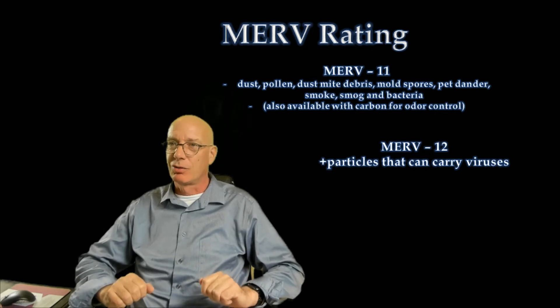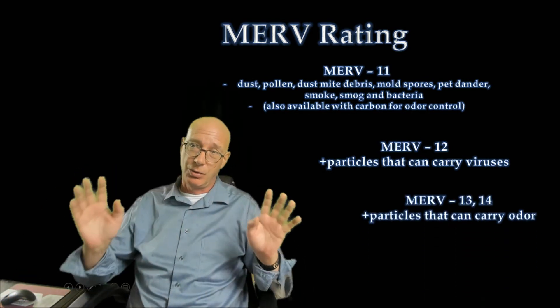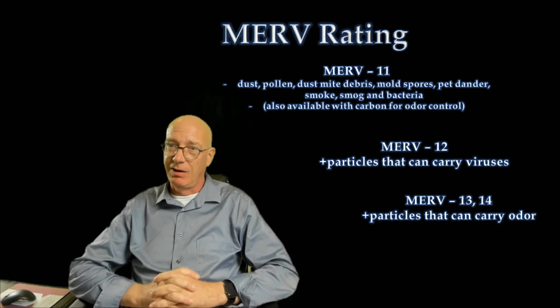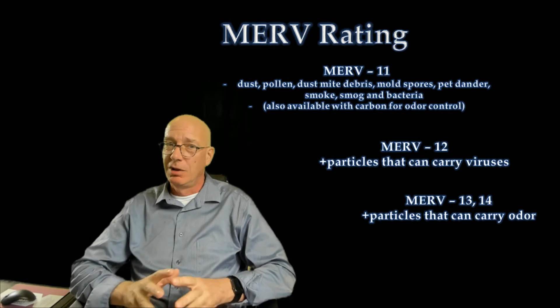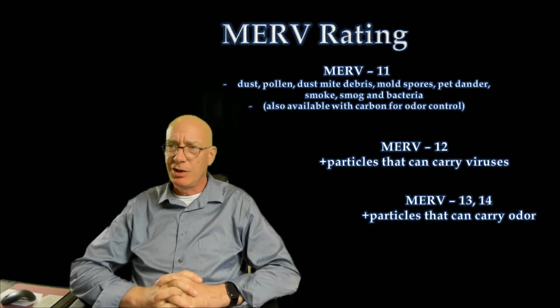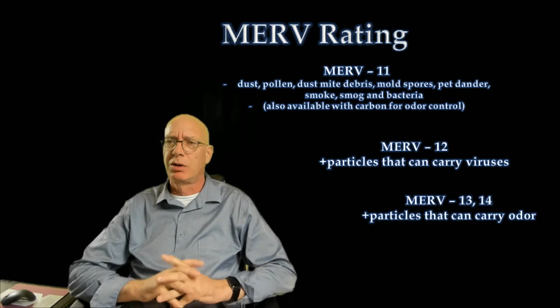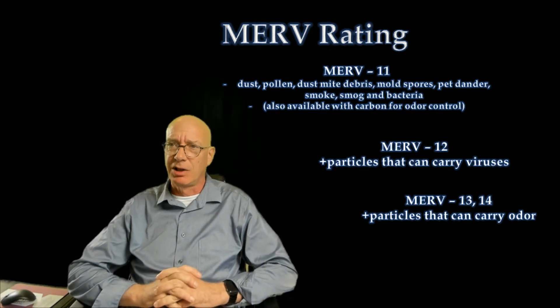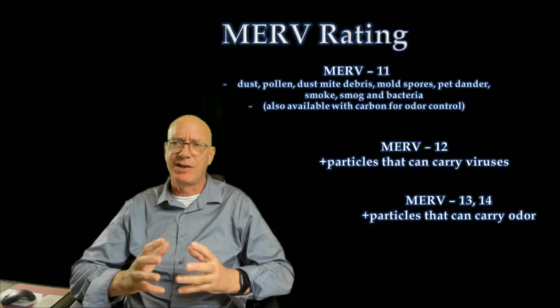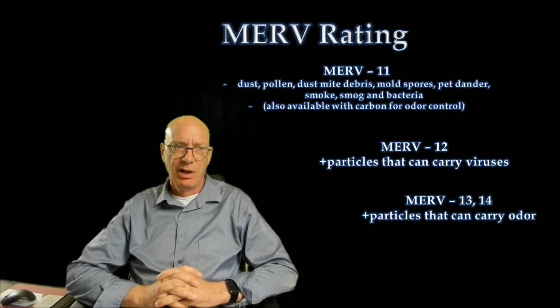There's a new filter on the market that I've recently upgraded to — a MERV 13 or MERV 14. This takes you down to a particle size below where viruses live, to the particle size that carries odor. So this is an alternative to a MERV 11 carbon-impregnated filter. My experience: MERV 13 filters in my home don't have quite as great an odor-removing capacity as a MERV 11 carbon-impregnated filter, but they have very high efficiency. The ones I'm using are rated at 96% for particles three microns and below — an extraordinarily good rating for a simple home HVAC filter.